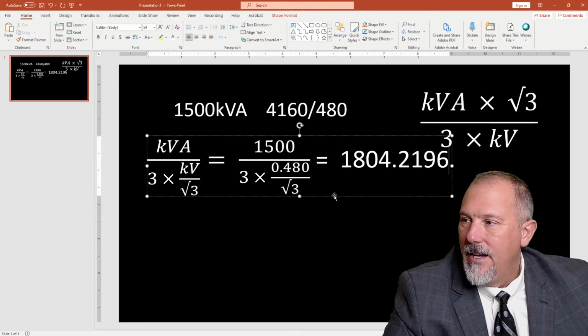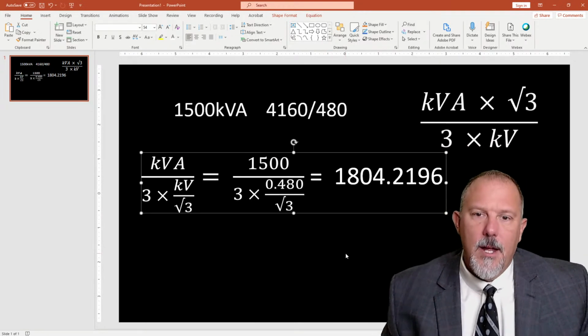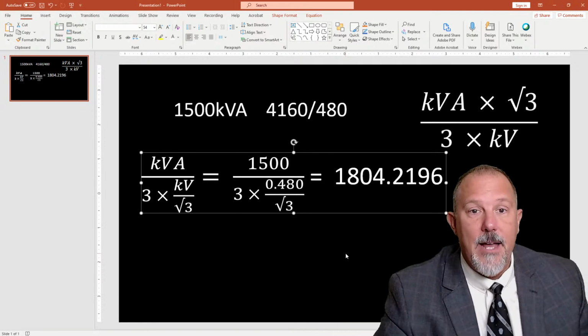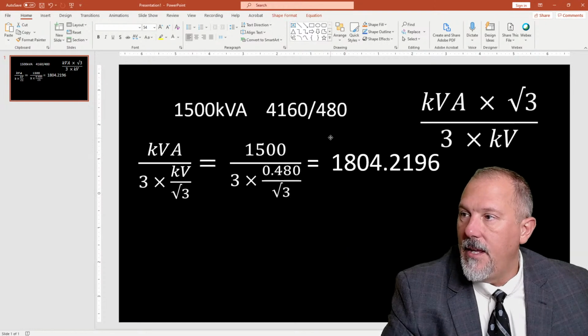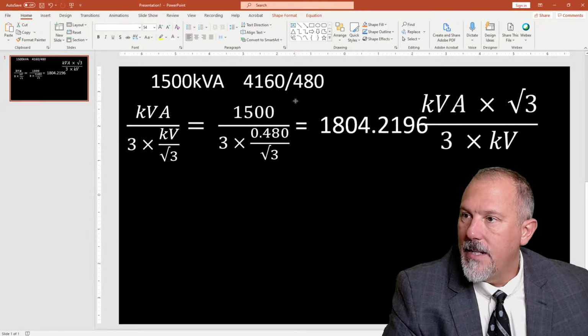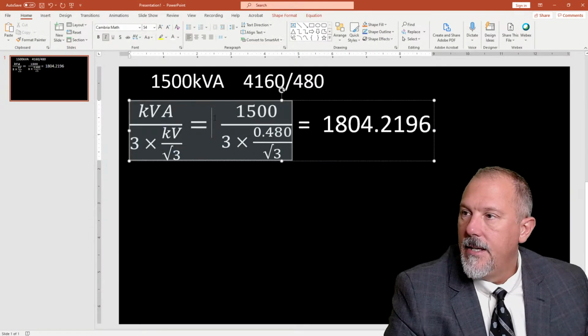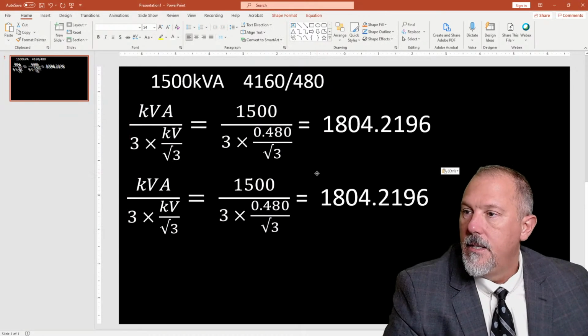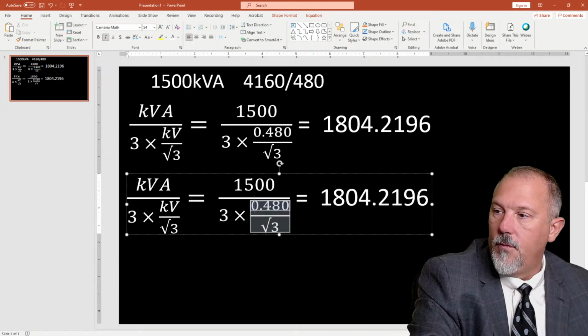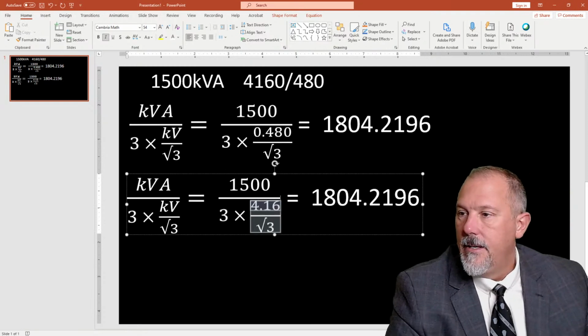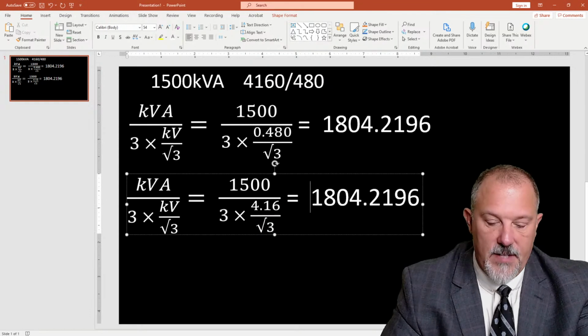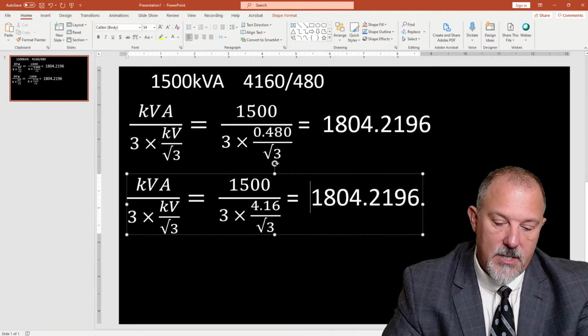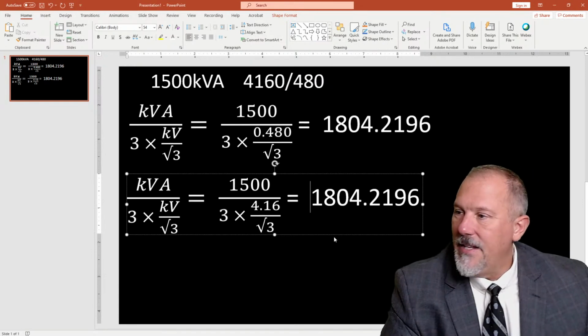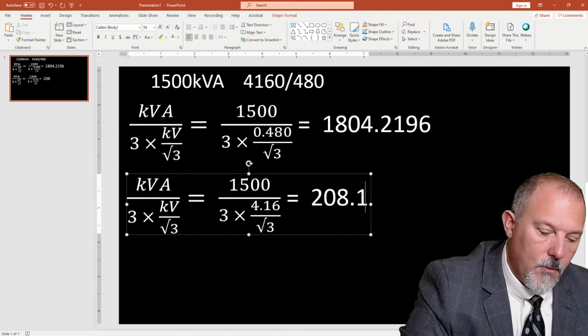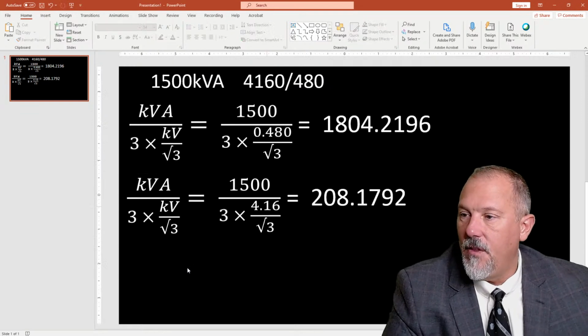1804.2196, but we don't typically say it's 1804.2196. We say the full load amps is 1804. Now, what is the full load amps on the primary? Let's do it the long way. So we're going to take this for primary. I'm going to delete that. For the primary full load amps, Control C, Control V. It's 1500, but I've got to change the voltage to 4.16, right? 4.16. So if I do it the long way, I take 1500, divide that by 3, divide that by 4.16, and multiply that by square root of 3, which is 208.1792.